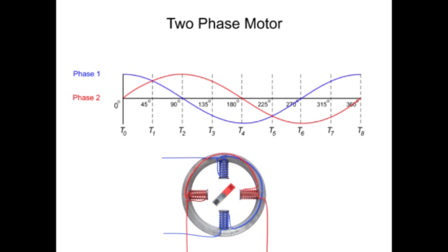At time zero, phase one produces maximum vertical magnetic flux and the rotor aligns itself vertically with the stator poles. Because phase two provides no current flow to the stators there is no horizontal pole on the rotor. At time one, phase one and phase two have equal amounts of current flow which creates a flux between the adjacent poles. This flux causes the rotor to turn 45 degrees to the left.